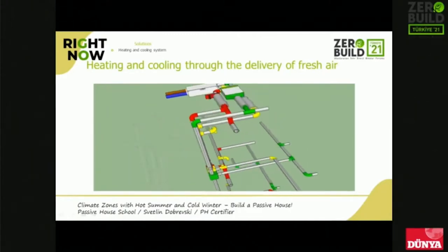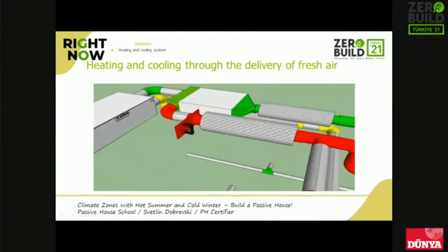The recirculation air is taken from the stairs and corridors in order not to circulate the humidity and odors accumulated in the service rooms. We also added a mechanical shutter valve to ensure the proper system operation. When the air-to-air heat pump doesn't run, it is closed, and where the heat pump runs, it is opened.